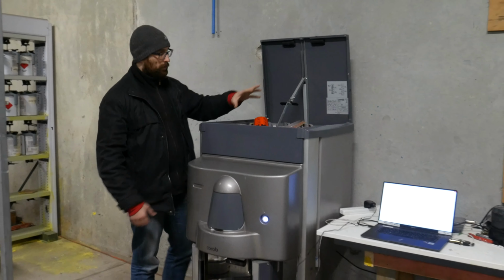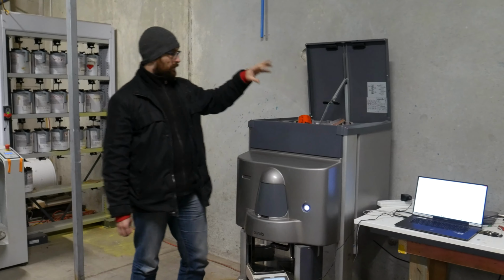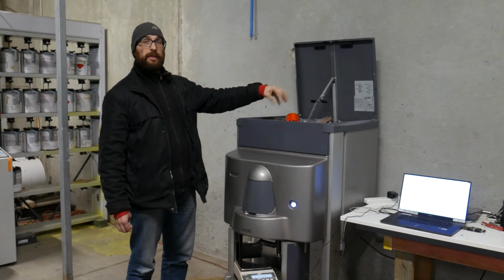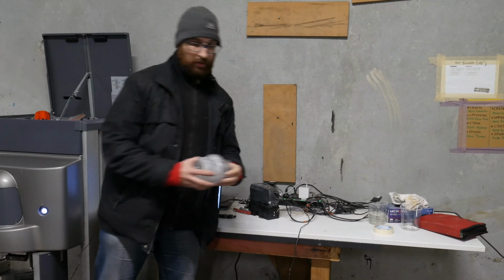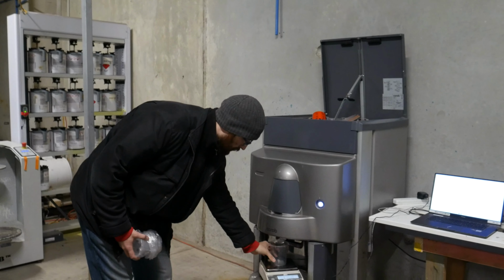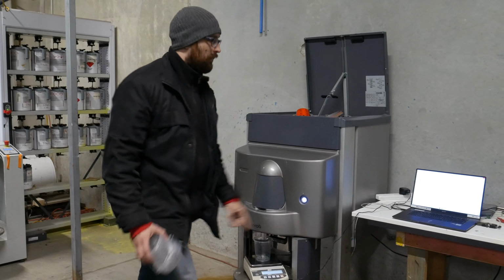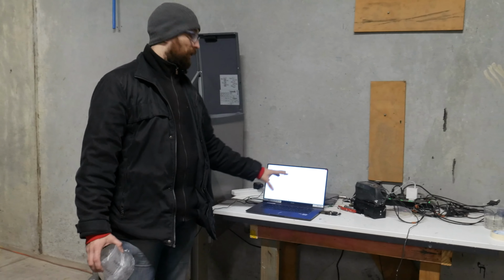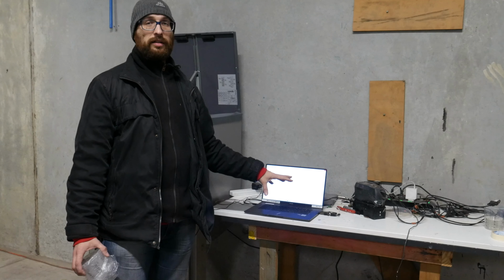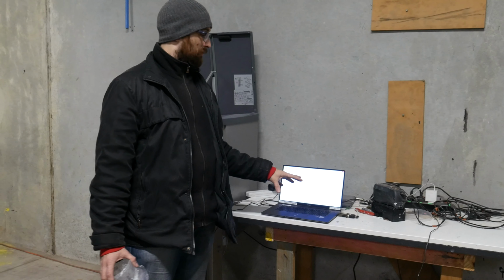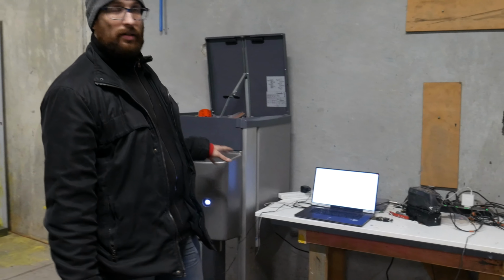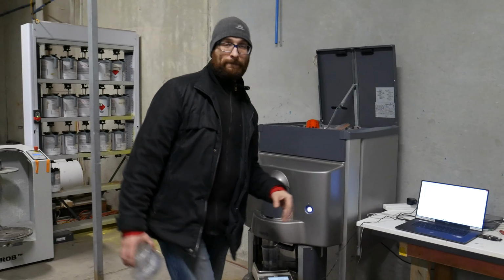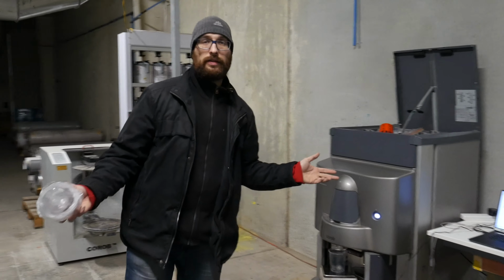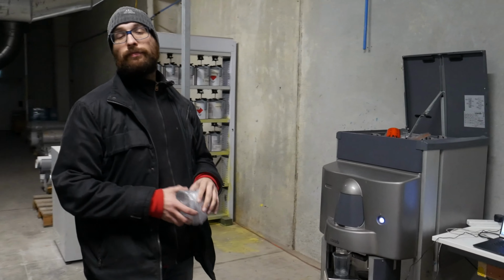And as long as the painting is dripping back, you can keep going with calibration: take a new glass, put it on the scale, tare the scale, go here, and initiate the calibration for another color. And then you should calibrate all colors one by one. Basically that's it. This is the whole concept of calibration.